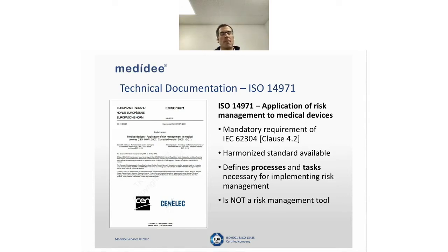So it basically tells you that you need to identify the different types of risk, or you need to identify the hazardous situation. You need to assess the probability. You need to assess their severity. You need to implement mitigation measures, control measures, and you need to verify that those measures are efficient. It's not providing you a tool, it's providing you principles that you have to follow and document that you have to generate. So this is something you also want to look at early, because when you're developing a product, risk is always one of the key characteristics you always have to consider.